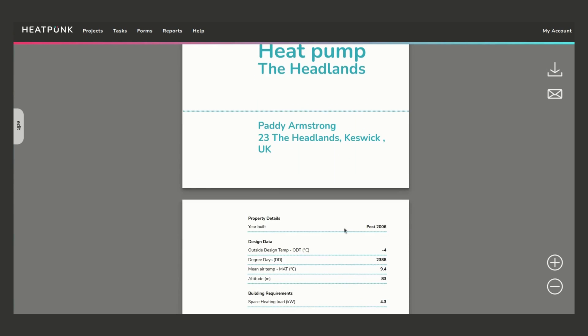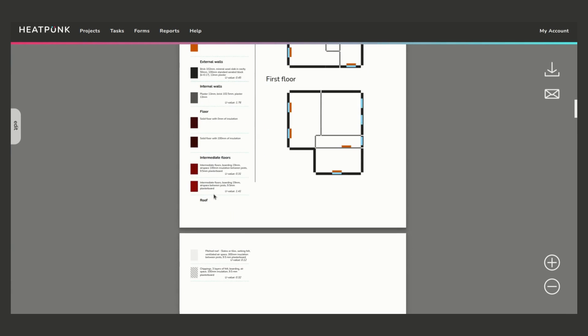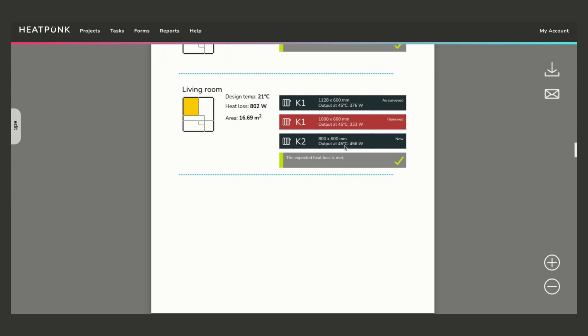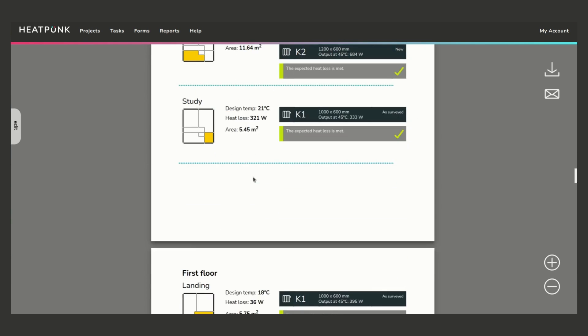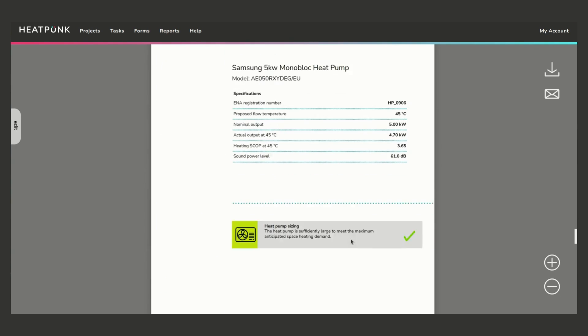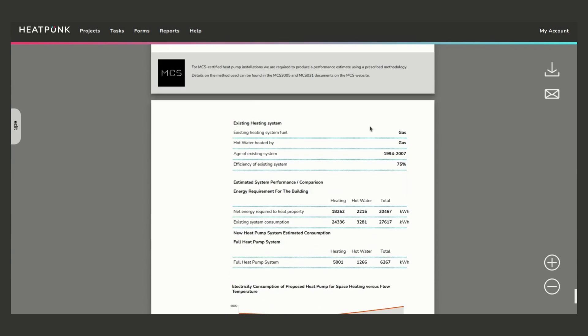This generates the overall heat pump report. It includes the property name and details, a survey with the layout and all the materials used, and a room-by-room breakdown giving design temperature, heat loss, area, and information on surveyed radiators' outputs at the chosen flow temperature. You can quickly check the upgrades, see what the difference is, and how each radiator meets the heat loss for each room. The report also includes information on the heat pump sizing check, the MCS sound check, and the performance estimate following MCS guidelines.